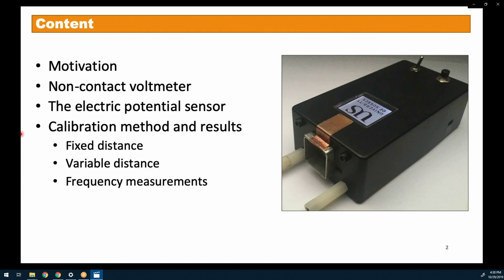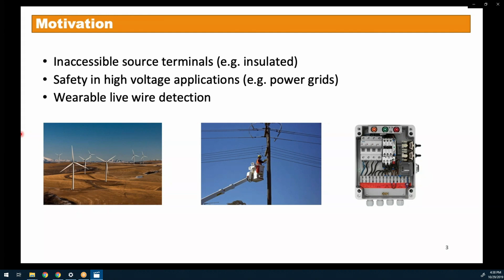So why do we need a non-contact voltmeter? There are cases where the terminals of a source under test are inaccessible. They are either insulated or encapsulated, so we can't touch them. But there are also cases where, due to the high voltages in a system, it's simply not safe to go in with conventional resistive probes and just touch tens of kilovolts with normal multimeters. So let's say power grids.